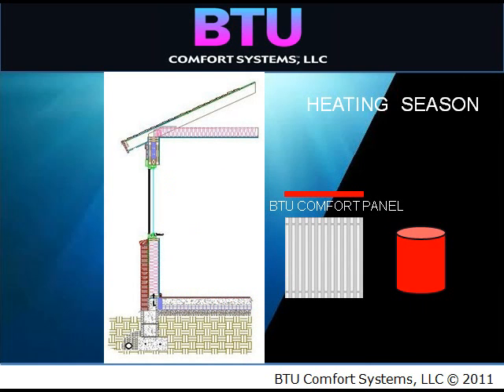In this example, a rapid response BTU panel heating system achieves the same comfort from the ceiling. There is a balance of mass that responds to temperature changes with great speed, yet has retention flywheel properties as well. Tests reveal the mass has properties to continue to provide conditioning for a little less than an hour without input. This system can go from heating to cooling in a matter of minutes. The surface temperature of the panel is not limited to 86 degrees like a floor system. This allows for more flexibility in overall system design.